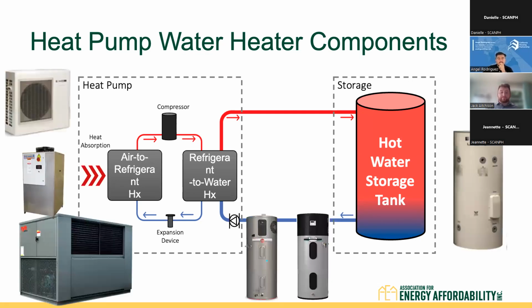Next slide, please. So just to show what this equipment looks like based off the previous slide, on the left, you have your heat pumps. Those, call them monoblock or packaged, are going to have all of your heat pump components within them. And then on the right, you have your standard storage tanks. And then in the middle, we have residential heat pump water heaters. Residential heat pump water heaters are integrated. So you have your heat pump on the top and your tank on the bottom. They're all one unit. So it's a little bit of a different configuration.